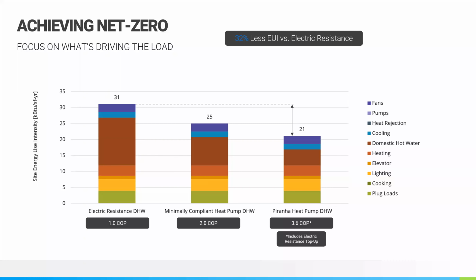That building became significantly more energy efficient over that time period, just by not going with electric resistance. And then even the next most efficient option, where they're running a minimally compliant air source heat pump water heater, they were still 16% more efficient by going with the wastewater heat recovery heat pump.